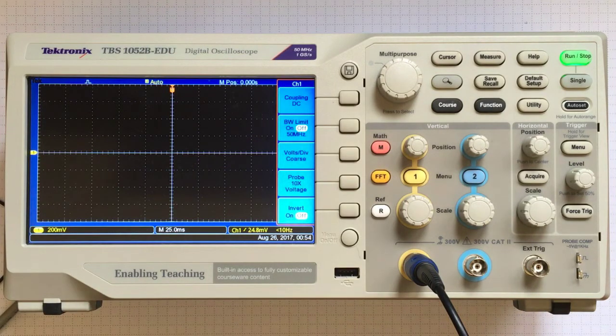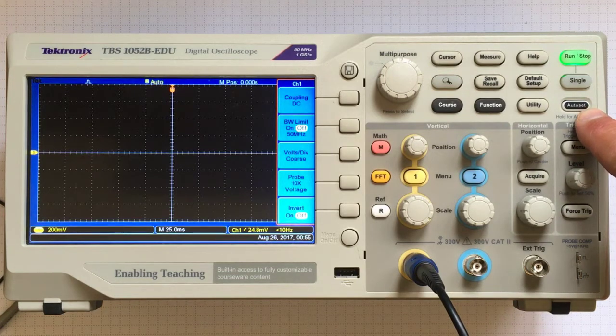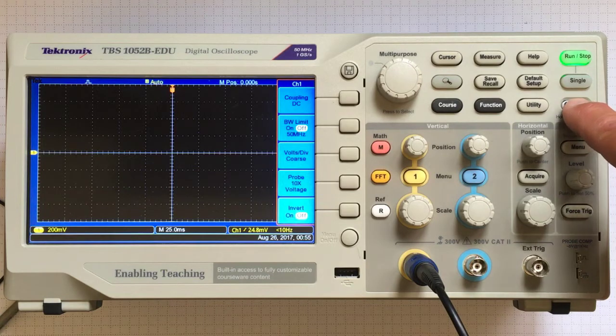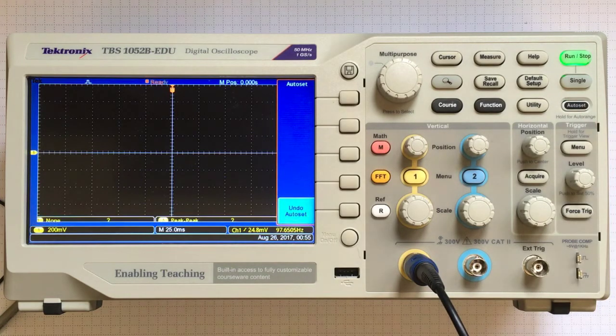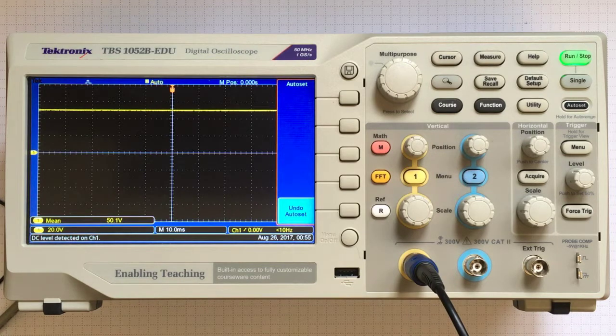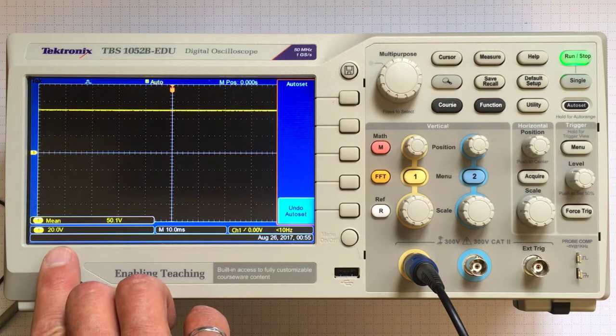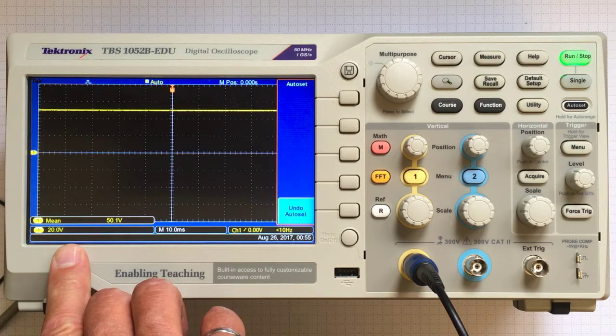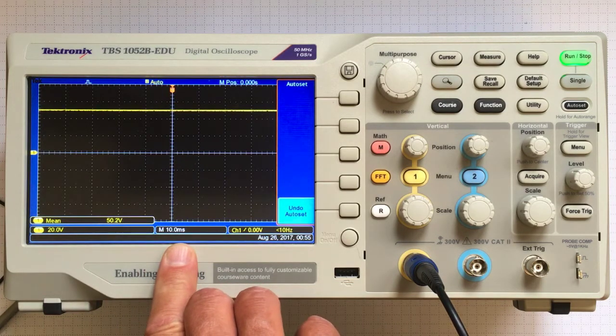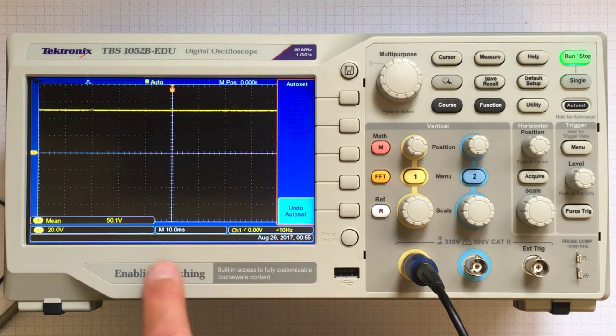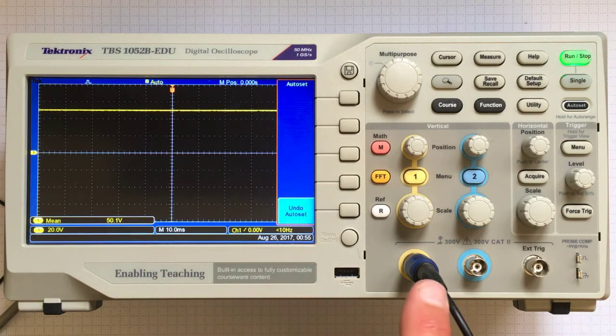Well, we don't have a signal anymore. What do we do? Well, if I didn't know anything, I would count on the machine to do the right thing, and I'd press this auto set button here and see what it does. It's going out, it's looking at the signal and figuring out what it looks like. It gets something like this. So it's on a 20 volt scale, it's looking at it at 10 milliseconds. That doesn't seem right.